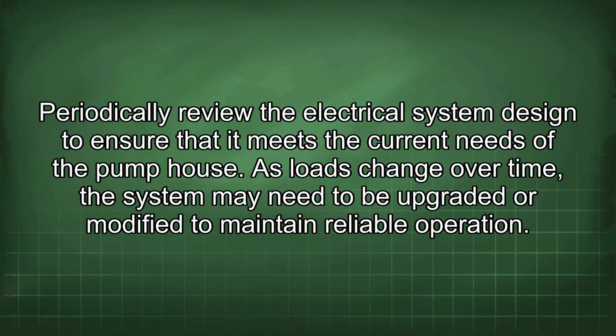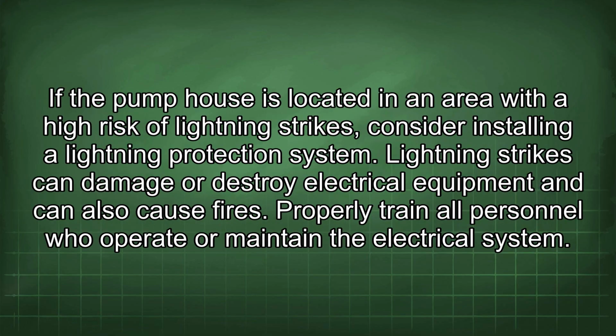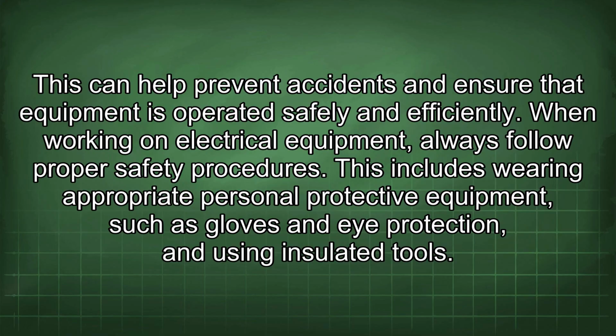Periodically review the electrical system design to ensure that it meets the current needs of the pump house. As loads change over time, the system may need to be upgraded or modified to maintain reliable operation. If the pump house is located in an area with a high risk of lightning strikes, consider installing a lightning protection system. Lightning strikes can damage or destroy electrical equipment and can also cause fires. Properly train all personnel who operate or maintain the electrical system. This can help prevent accidents and ensure that equipment is operated safely and efficiently.